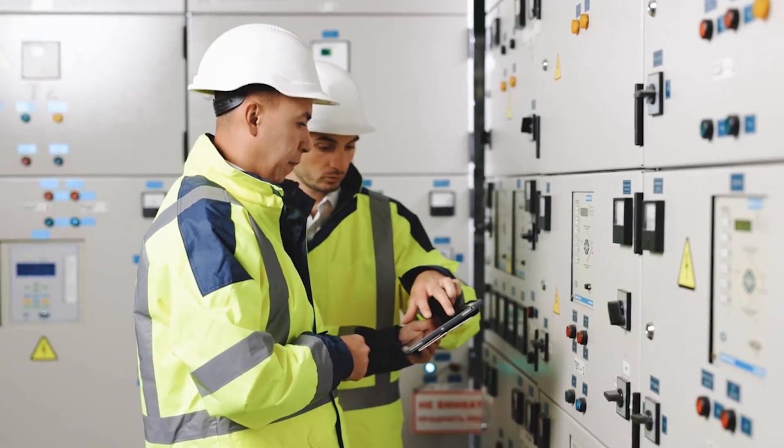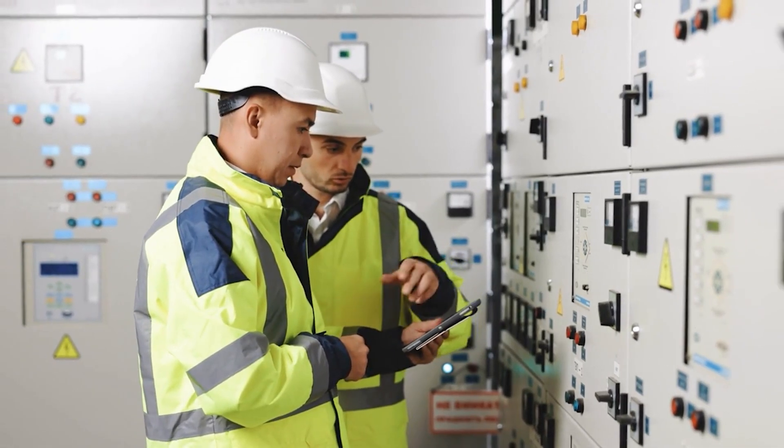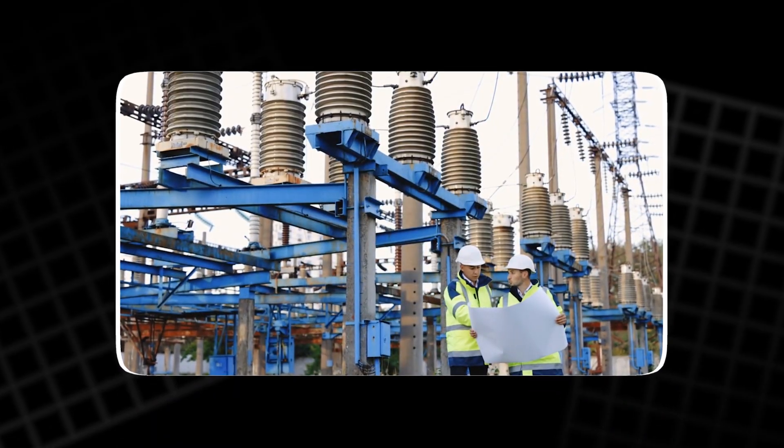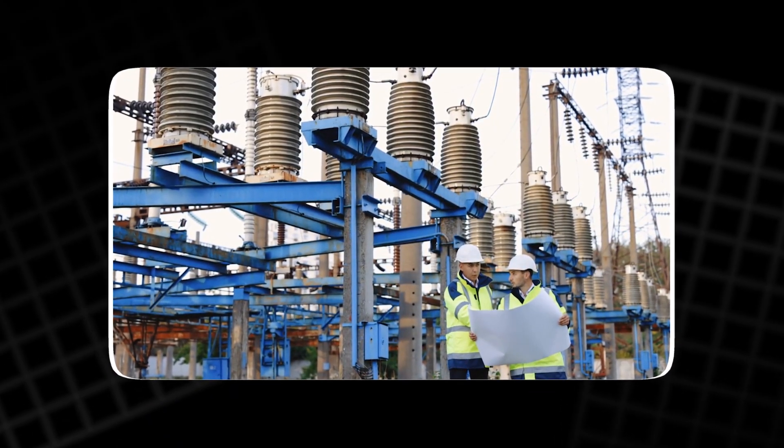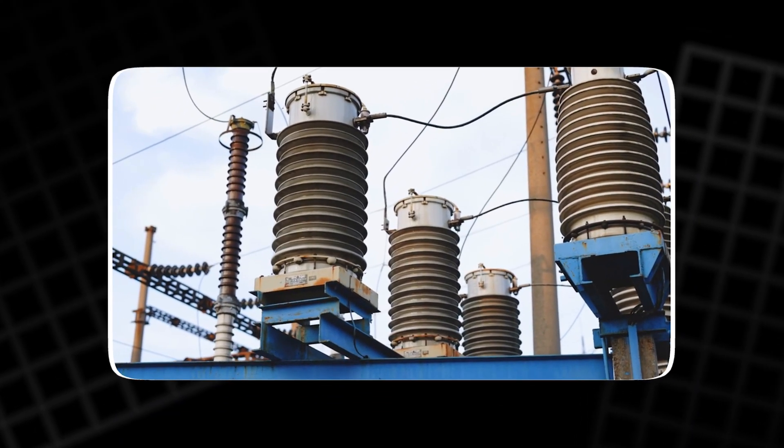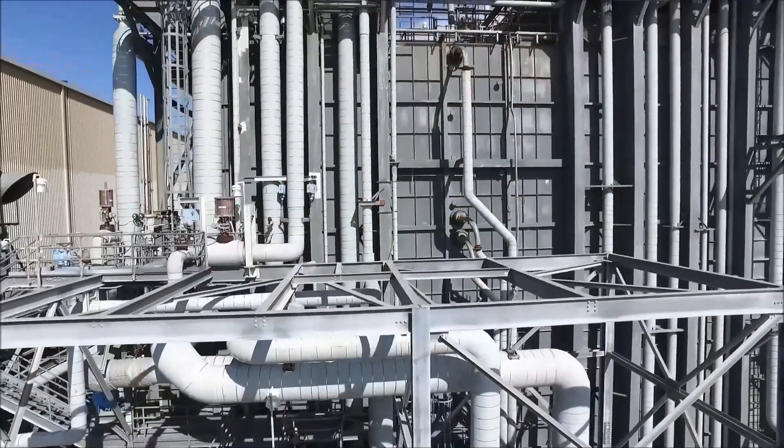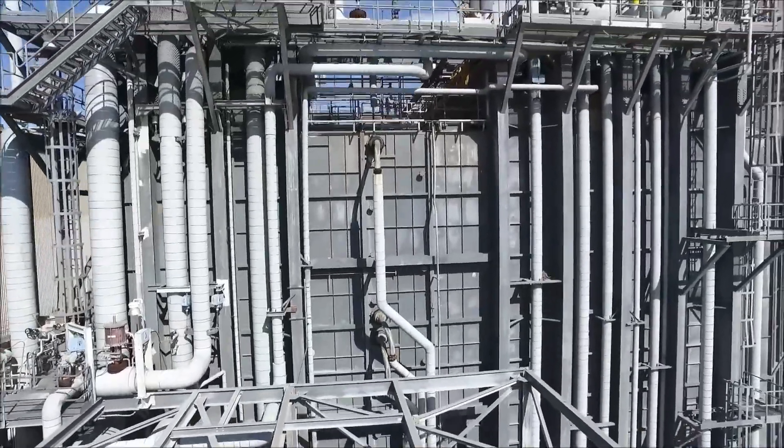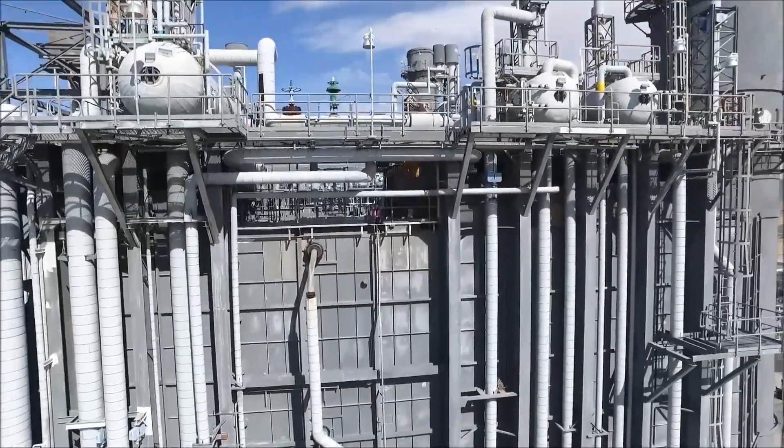The root cause of the failure wasn't an equipment malfunction in the traditional sense. Rather, the disturbance was exacerbated by a combination of algorithms and configuration settings within the power conversion equipment. These systems reacted in ways that were not anticipated when they sensed the initial fault.